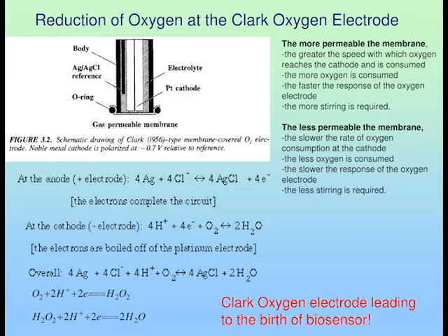So normally when we do this kind of measurement, the solution is always being stirred, but at a constant speed. When I say constant speed, it means from sample 1, sample 2, all have to be the same speed. Because if you stir faster, you're going to get higher current, because the response is faster. More oxygen is going through. Those are the conditions you have to take note of. Okay, let's go to the next one.